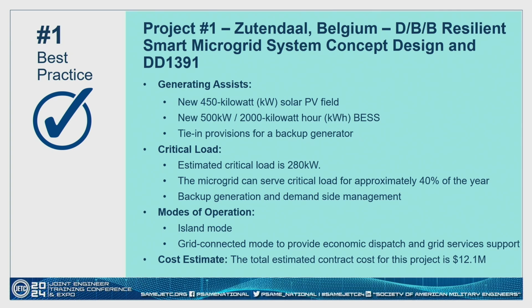The original scope for the 1391 we got was solar PV with battery energy storage. Throughout the concept design, we determined that just the solar PV and the battery energy storage would not allow for full capture of the critical load they had. So we did different iterations of a power study and determined the installation will need a backup or roll-up generator to connect to this in order to capture that load.